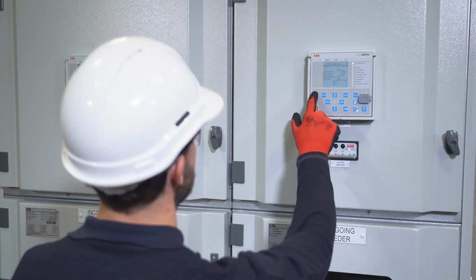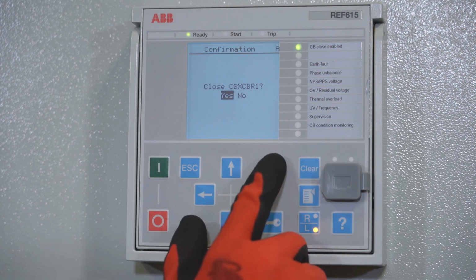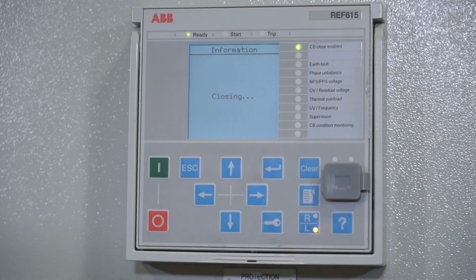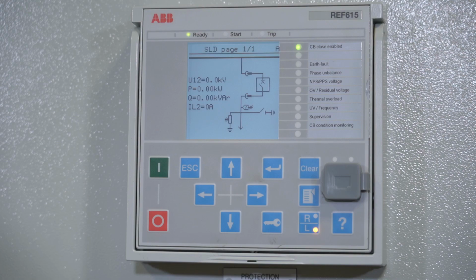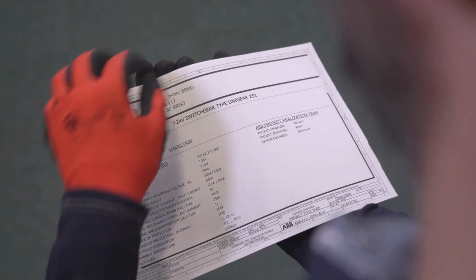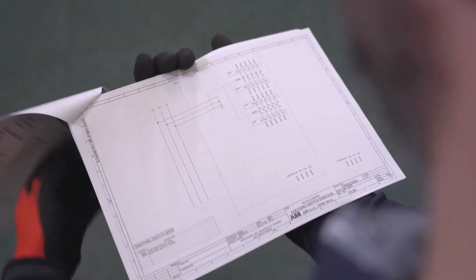The closing operation is typically interlocked, and all the interlocking preconditions must be fulfilled prior to closing the circuit breaker. If the circuit breaker doesn't react to closing commands, check the interlocking signals.